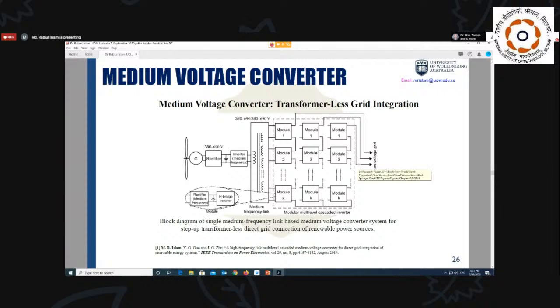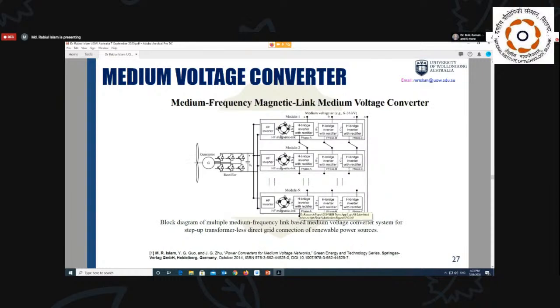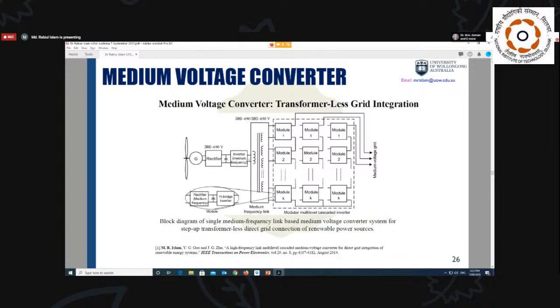In this case, we can eliminate the step-up transformer and line filter. That means this inverter or converter can generate medium voltage output with good quality. Maybe this single magnetic link cannot handle 10 megawatts of power, right? Just for your information, this is just a magnetic link. It is not stepping up, that means the turn ratio is 1:1, and it just produces multiple isolated sources from a single source and also provides galvanic isolation.